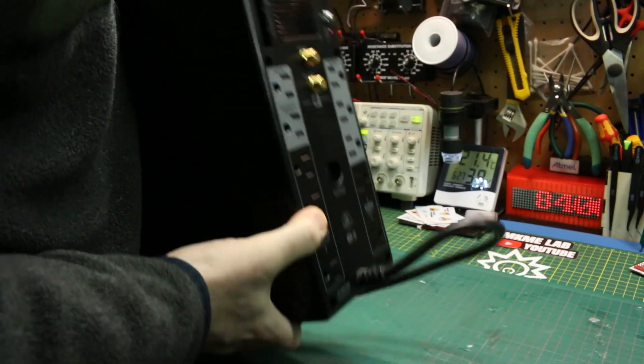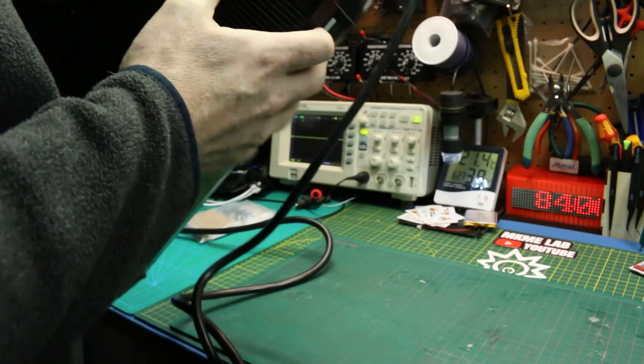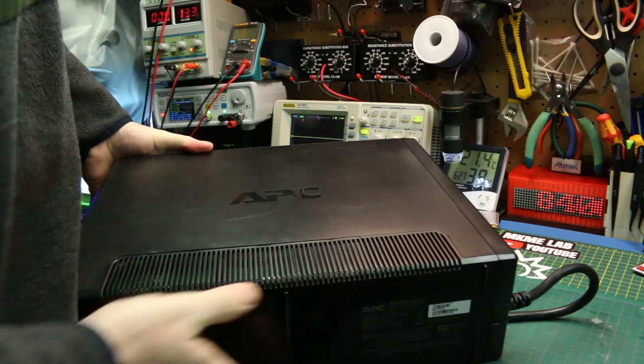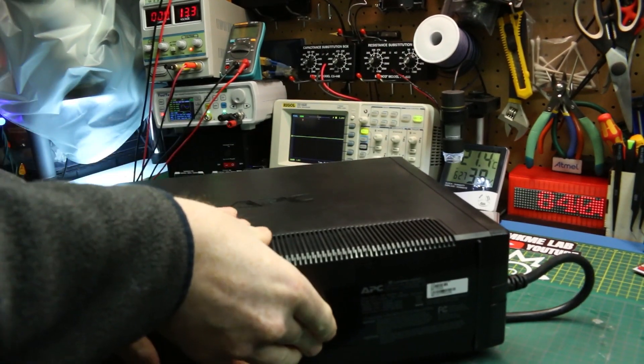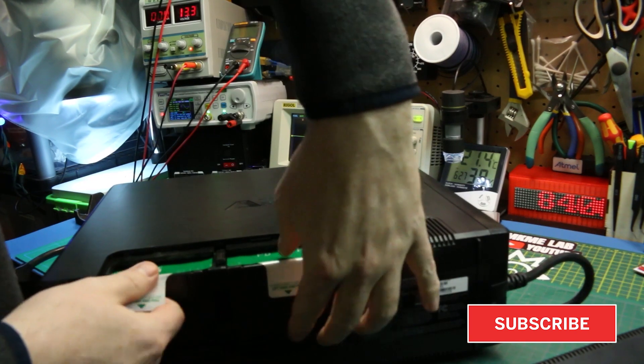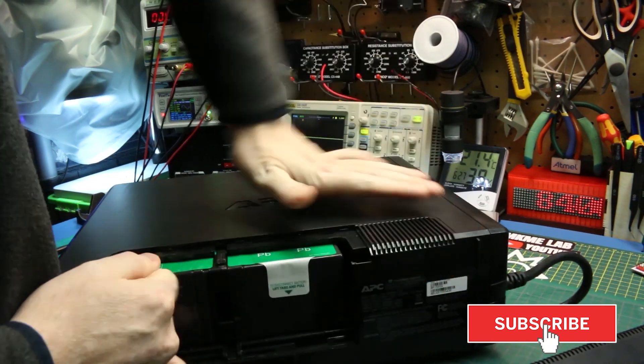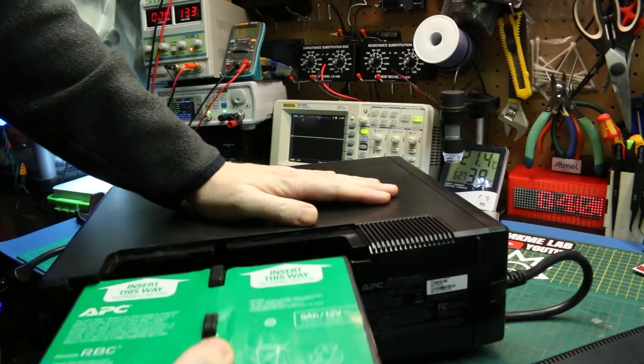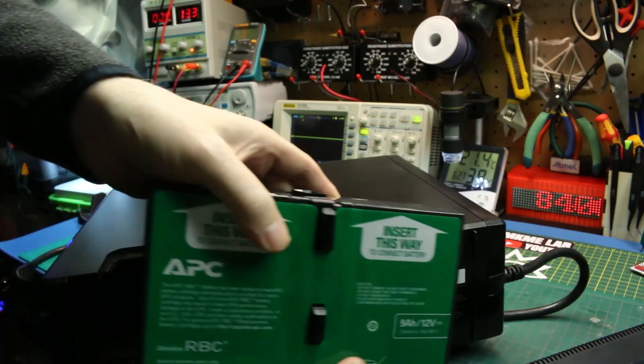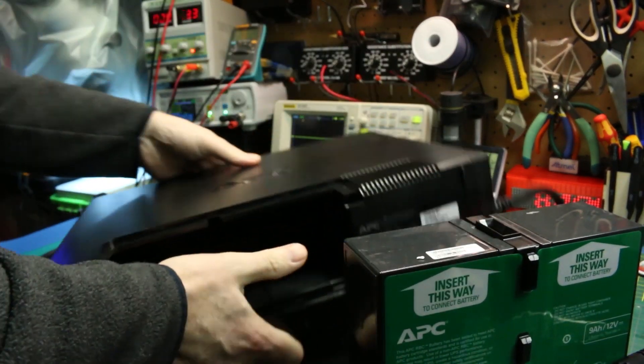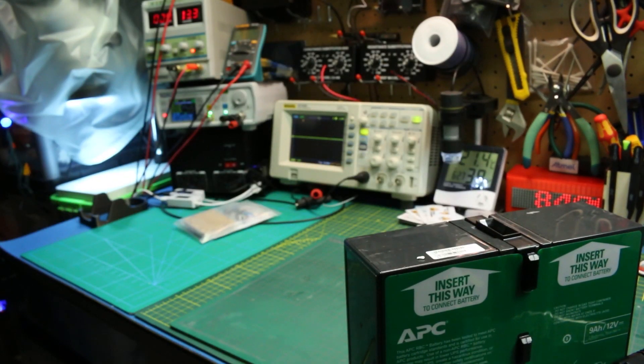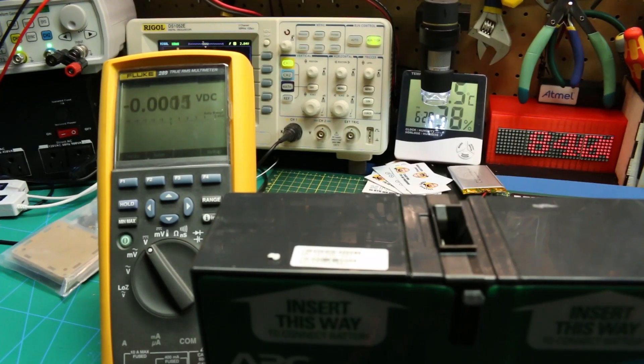As with any repair, first step is we want to do a quick visual of the unit. Well, since it's a UPS and relies mostly on the batteries, first place we want to look at is the batteries. There's two batteries in this unit side by side, kind of attached together, and they look pretty good. They're not swollen or cracked or anything.